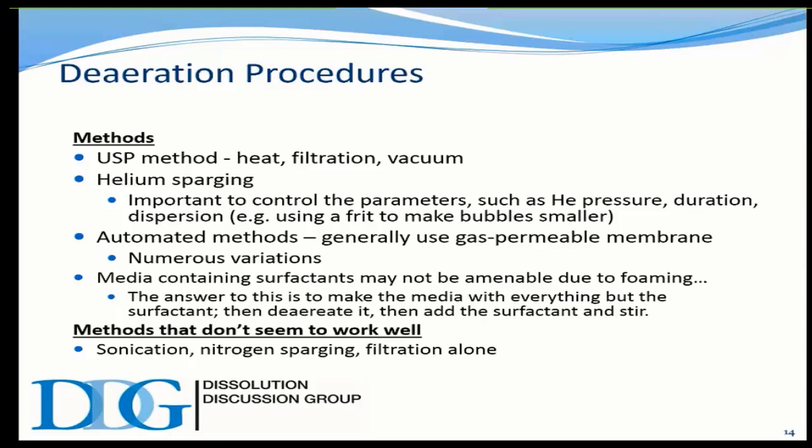There's been a number of papers written, and I've summarized some of the methods that have been used in the past. But these really boil down to mostly some type of method involving heat, filtration or vacuum, and the USP captures that best, I think. Sometimes it's not just raising temperature or not just filtering or not just applying a vacuum, but doing a combination of some of these processes can be quite effective.